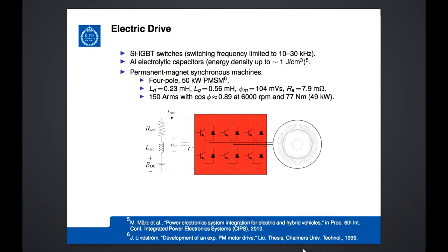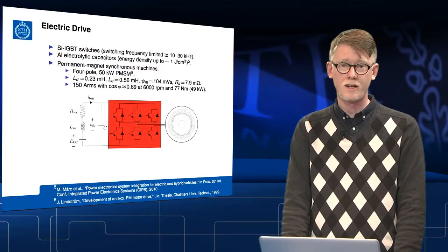If this machine operates at 49 kilowatts, 6,000 RPM and 77 Newton meters, the phase current is around 150 amperes RMS and the power factor around 0.89.